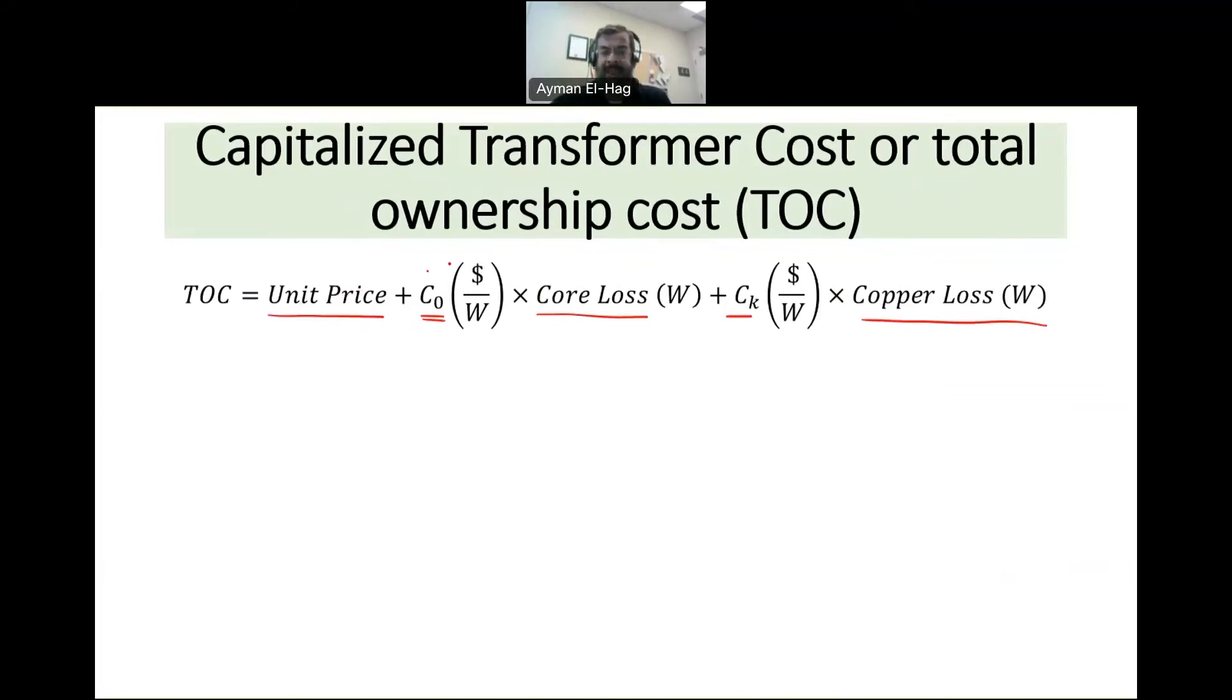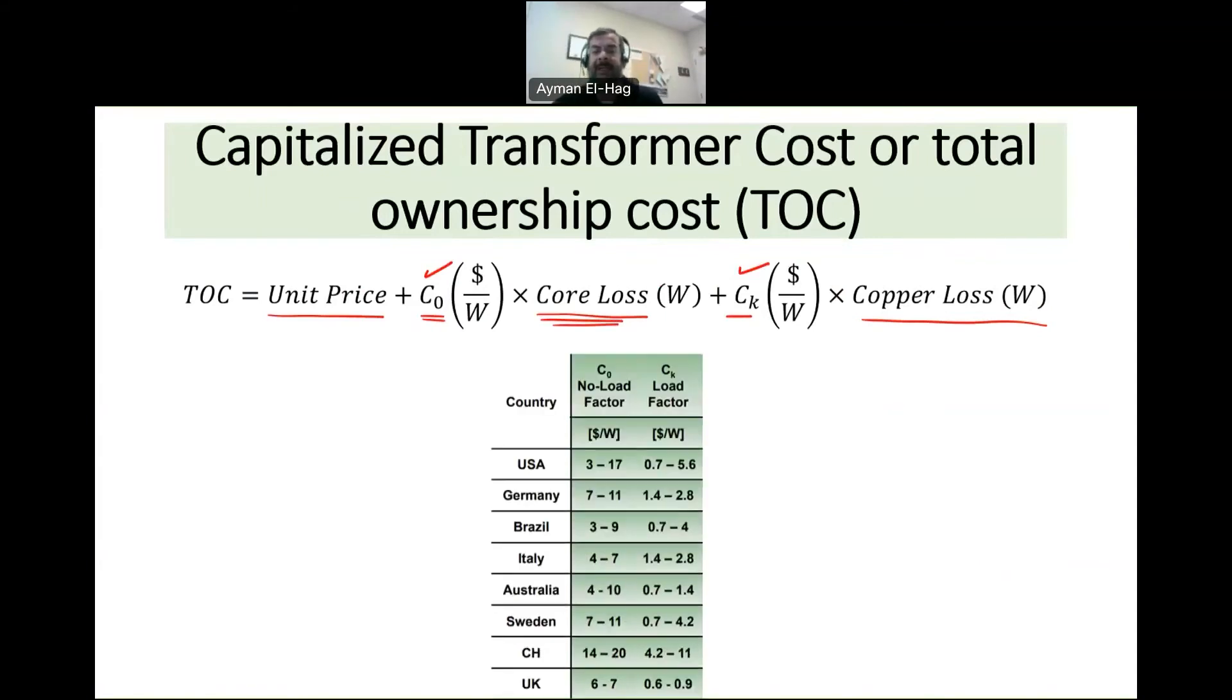Now I think with this understanding you will figure out that C₀ should be larger than Cₖ, or the core loss should be more important than the copper loss. Why? Because the core loss stays 24/7 all the time - we have the maximum core loss - but the copper loss is varying, it's not constant.